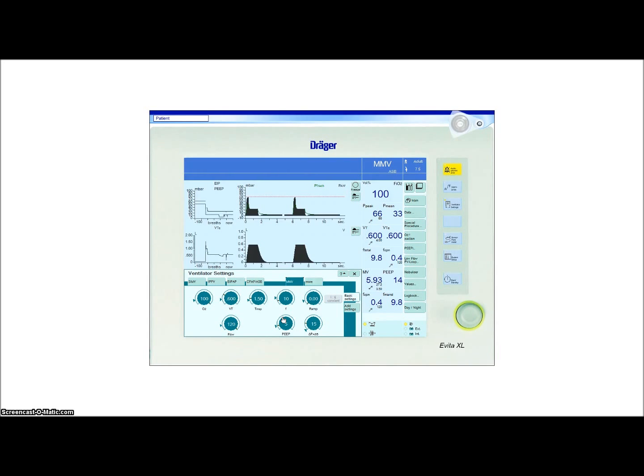We have PPS, proportional pressure support, but we're not going to go into that today. I'm going to leave you with some waveforms and allow you to watch as I forward the mode, and we'll go ahead and review IPPV, intermittent positive pressure ventilation. Patient is on full support. He doesn't breathe. He gets the set rate at a set tidal volume, at a set inspiratory time. If he wants a breath, he can take that breath. But in IPPV, even though he takes a breath, it's called an assist breath, because he's only going to get the set tidal volume and the set inspiratory time.